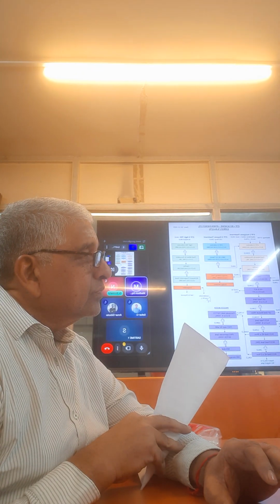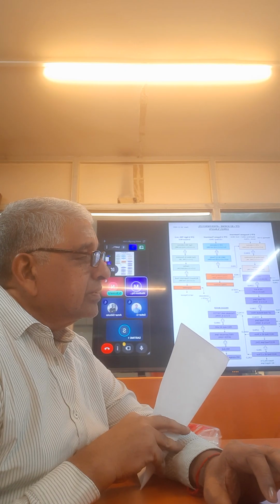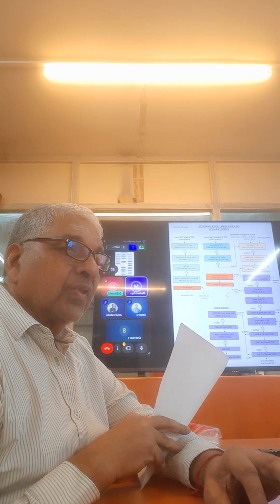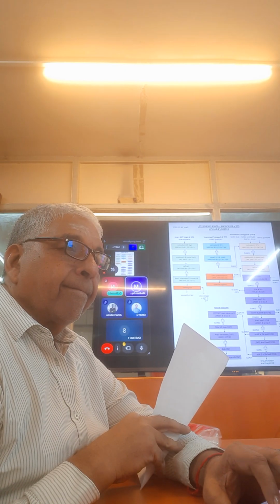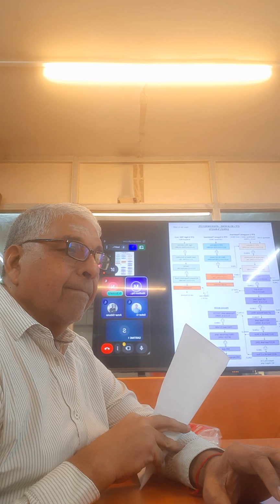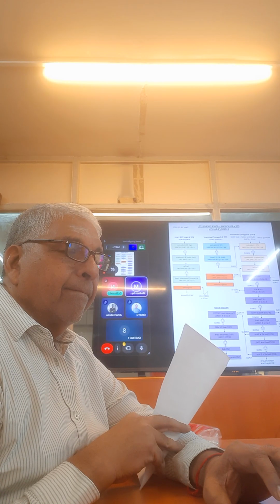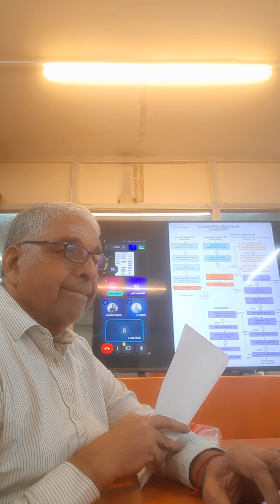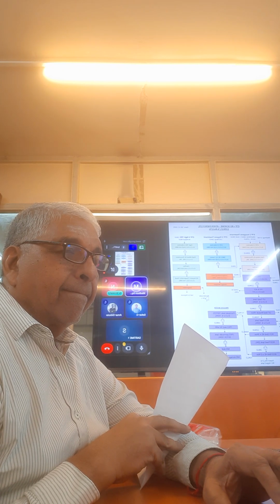With the filter press, I feel there is a lot of manual work involved, and the surroundings become dirty. The decanter gives a better result, but as you said, it costs almost, not even 3 to 4, sometimes 6 to 7 times higher. Yes. Technically it is not a problem.